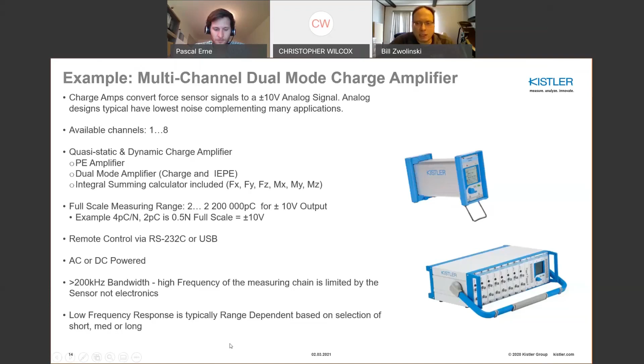I mentioned rangeability, and just a simple example of rangeability. What you see here in the piezoelectric sensor, it might be a 10,000 Newton sensor, and you have a simple cable and a charge amp. You can range that sensor for anything from, I just show an example down to 1 Newton. And what you see here is the actual noise voltage, RMS noise voltage, actually decreases proportionally as a function of measuring range. So you really get what we call the magic of rangeability. So you actually get a very low noise solution as you go down in measuring range, and it's really the attribute of an external charge amp that's working for you.